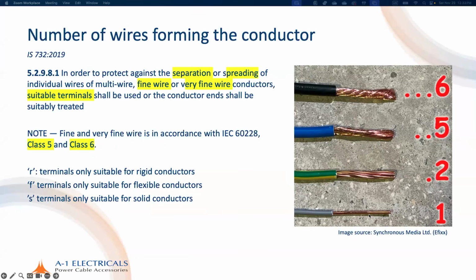Yeah. So class 1 is a rigid conductor, solid single strand. Class 2 is a multi-stranded conductor. Class 5 is a fine stranded. Class 6 is a very fine stranded. For earthing, you can use any of these as long as the correct type of lug is used. For example, for class 5 and class 6, you need to have the correct type of bootlace ferrule. Of course, in India, we recommend that we stick to class 1 or class 2 only because of the consequence of the connection and the higher resistance of class 5 and class 6 conductors. But yes, you can use this with the correct type of lugs and terminals. So that is an important part of it. In terms of whether you can use it for earthing, again, the sizing comes as per IS 732 that I just showed.